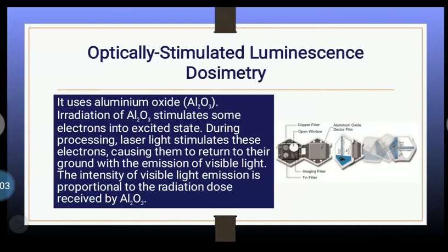Okay, so, I know may question kayo. How many TLDs or monitoring devices are used per department? So, sa UEP, kung mapansin niyo, we are 3 radiologic technologists, but we have 4 personnel monitoring devices. We have 4 OSLs. Because kailangan, there is a control badge. Yung tinatawag nating control badge, which is parang cumulative siya na na-receive for each RadTech. Parang confirmatory.